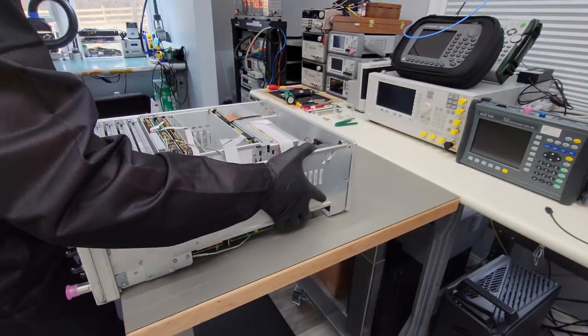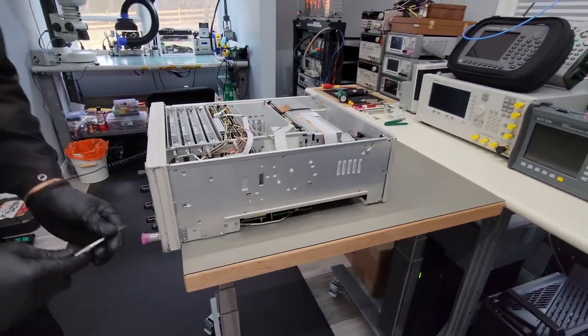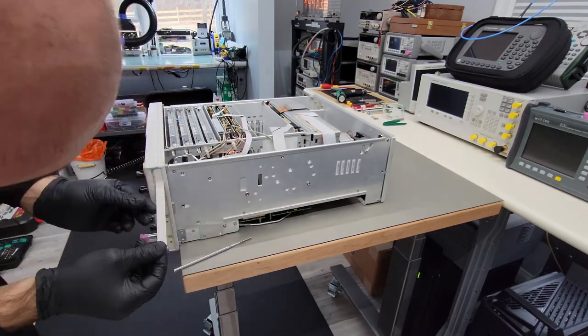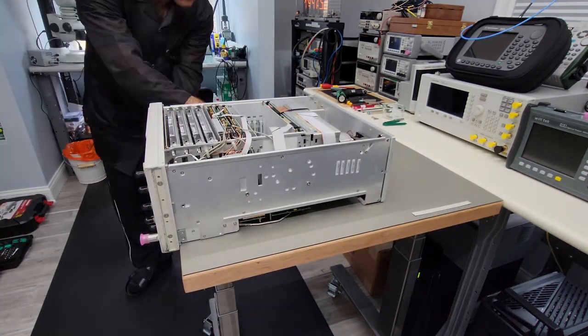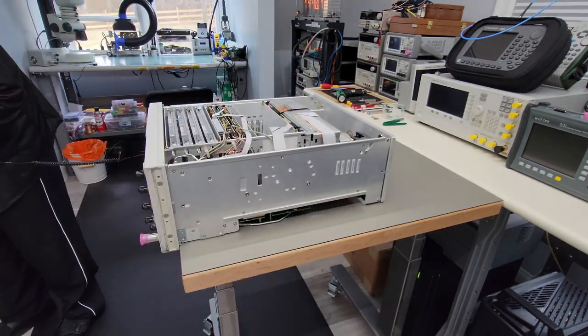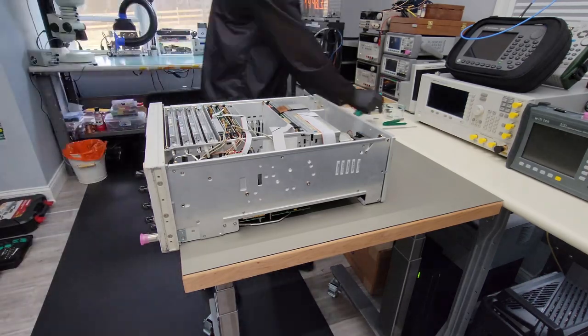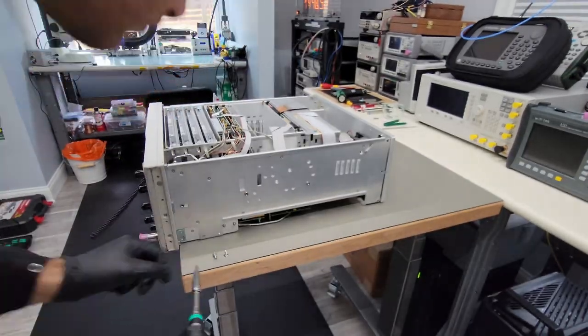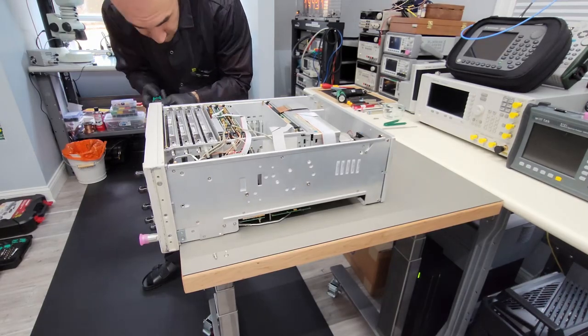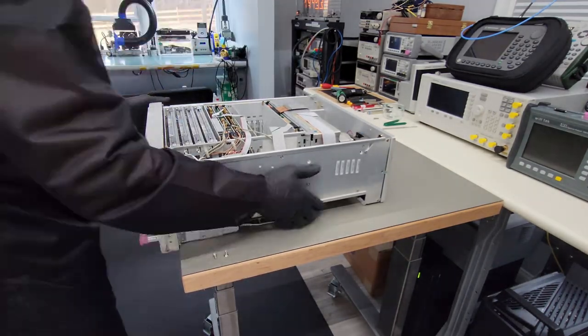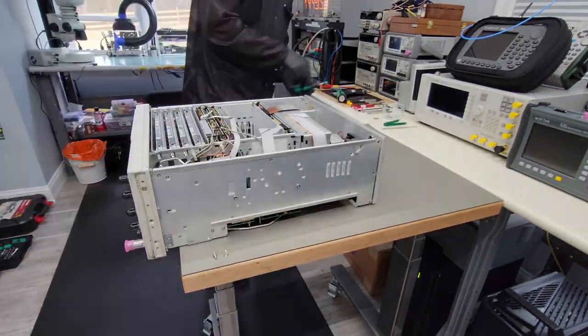So dropping the front panel on the PSG is a little bit of a fiddly process. You have a number of screws on different sides of the instrument, and then you need to carefully slide it off of the chassis and the main RF connector, while being careful not to apply too much stress to the digital connectors going to the front panel. So it's a little bit of work, but patience is the key.